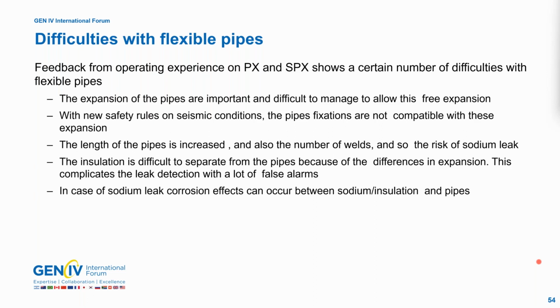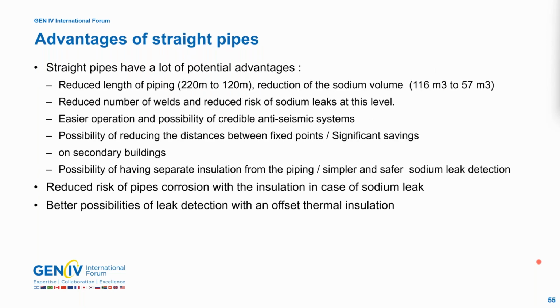And if the pipes are moving, we cannot separate the insulation from the pipes because there are differences in expansion. That complicates the leak detection, with a lot of false alarms. In case of a sodium leak, corrosion effects can occur between sodium, insulation and pipes. We have seen this type of corrosion on Phoenix.